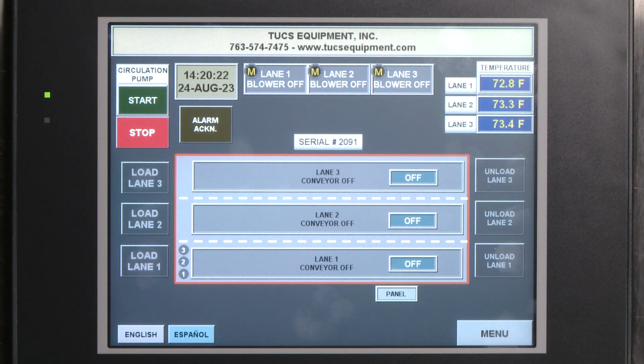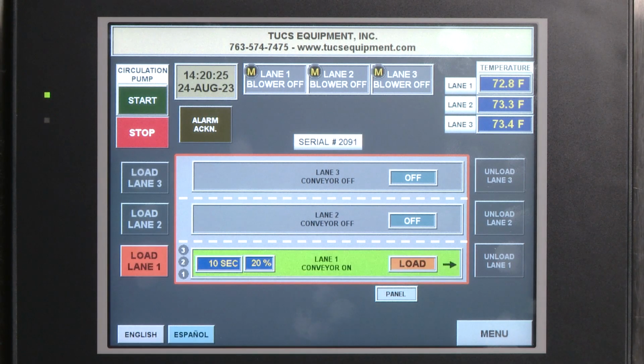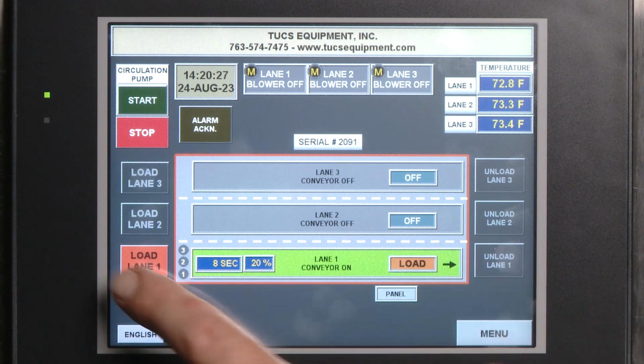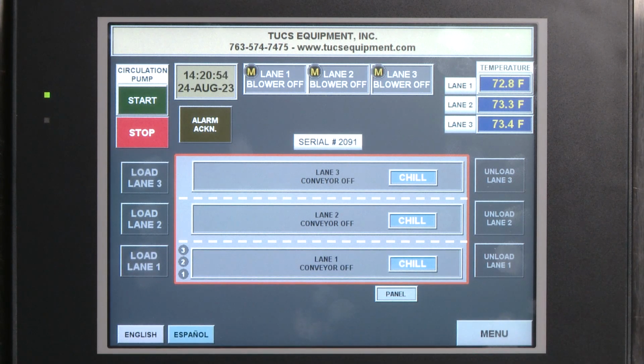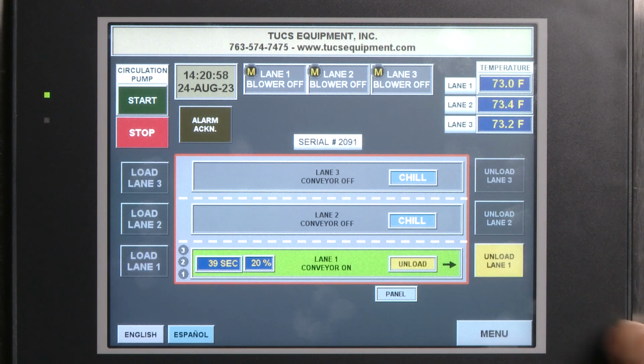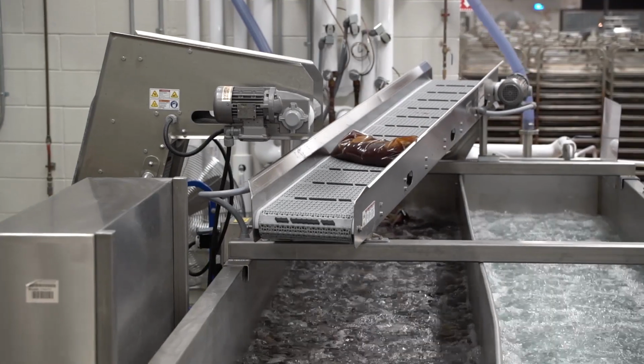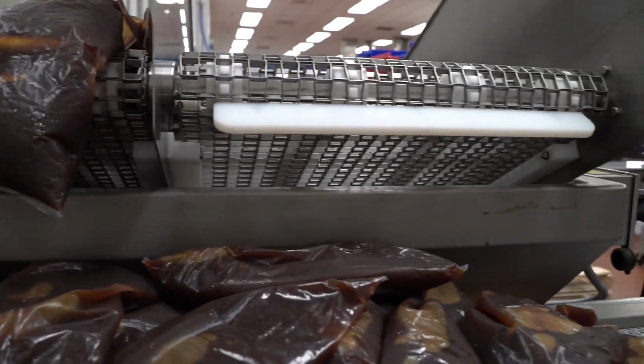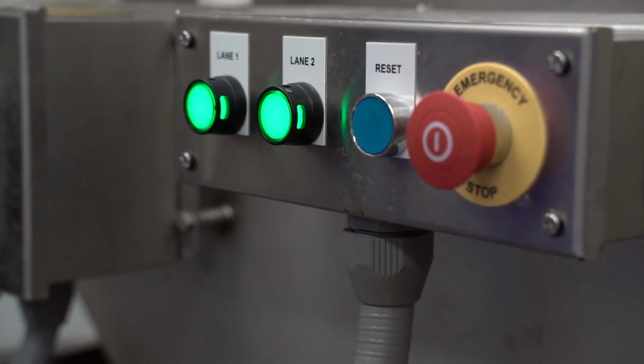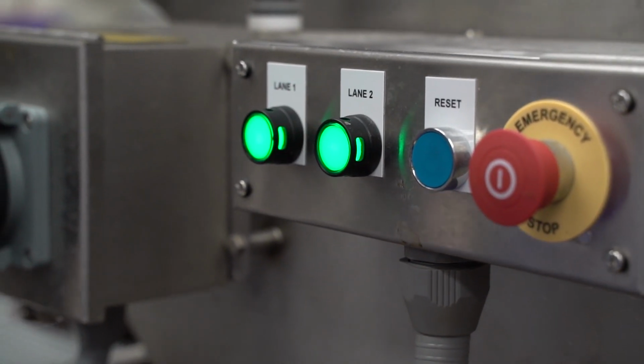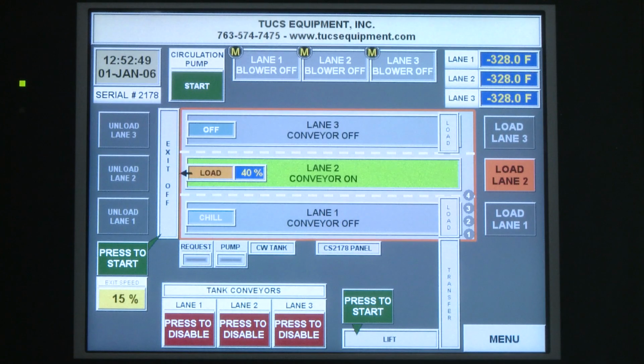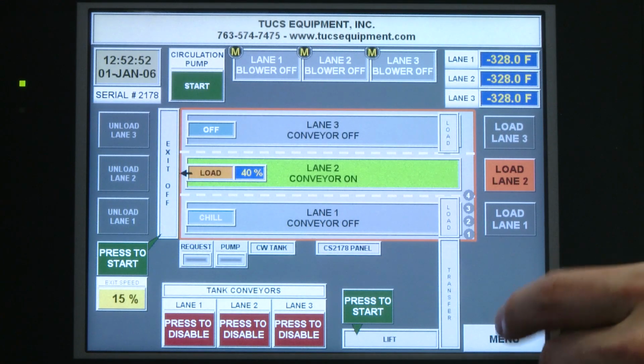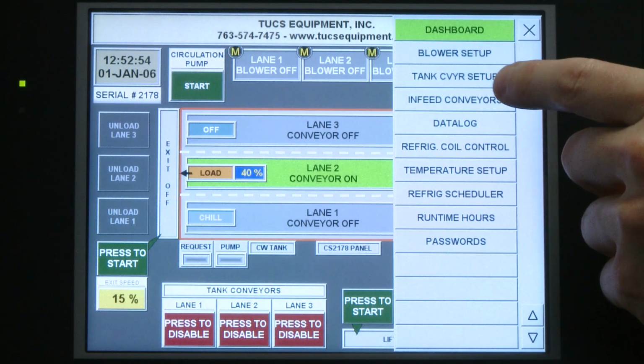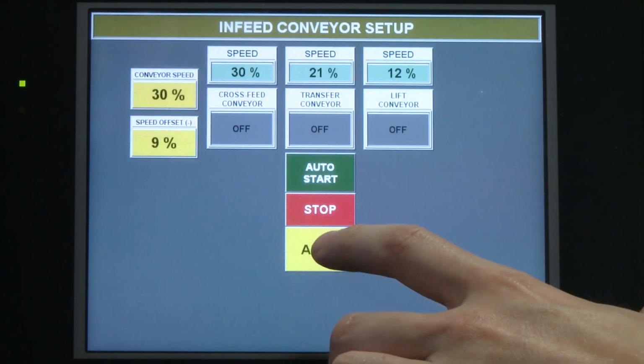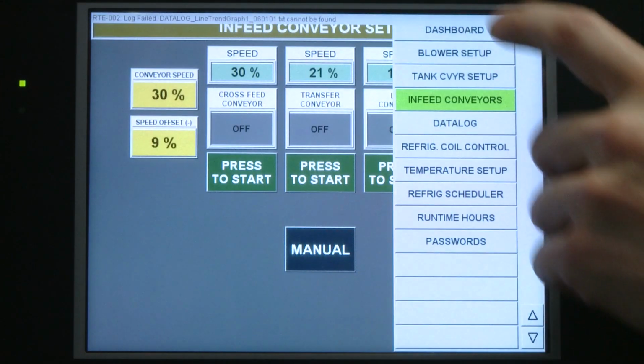The Load buttons select the lane to load and will toggle between 2 states, load and chill. The Unload buttons toggle between 2 states, unload and off. The in-feed and exit conveyor are started and stopped with the Press to Start button next to the conveyor while in auto. If in manual, they are controlled from the conveyor setup screen, and an In-Feeds in Manual message will be displayed in place of the Press to Start button.